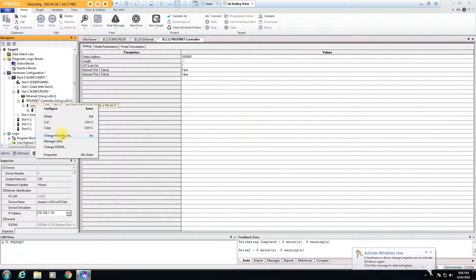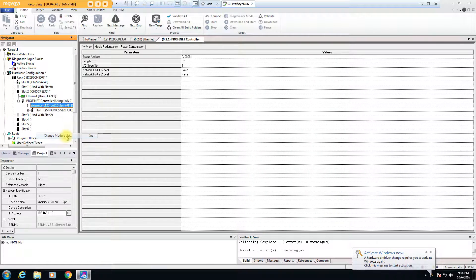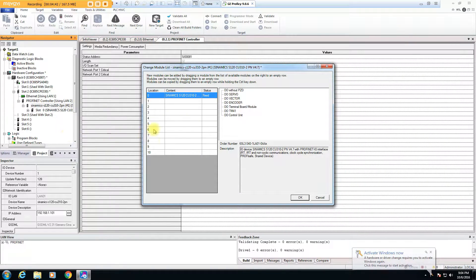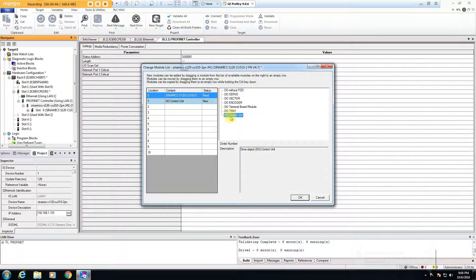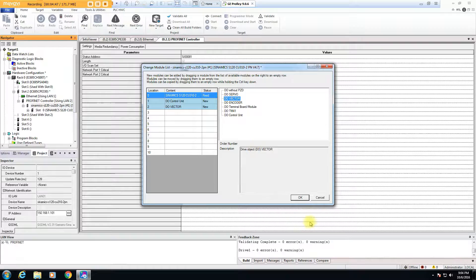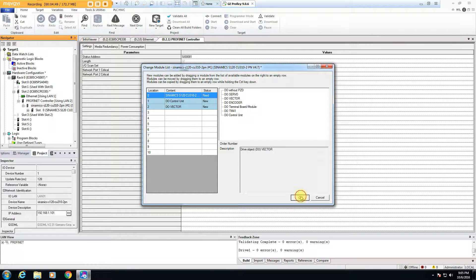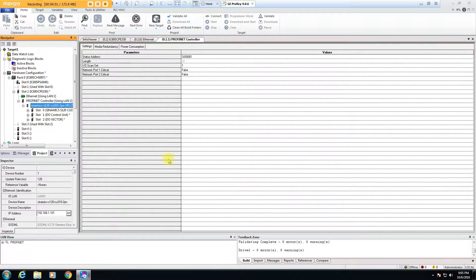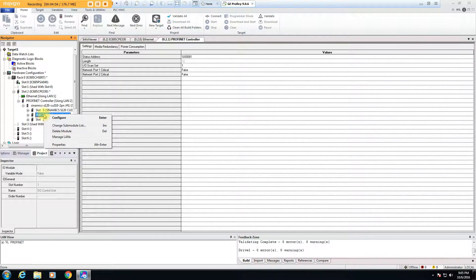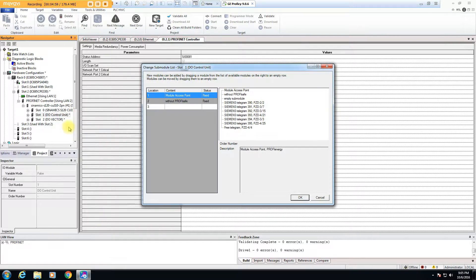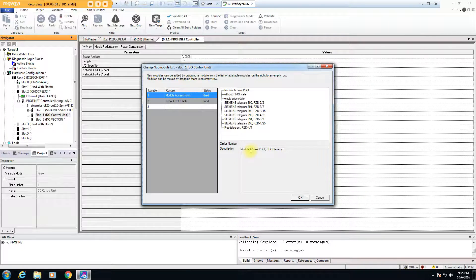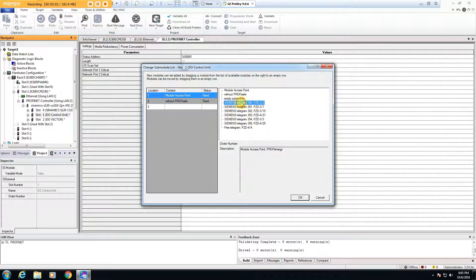But then you gotta go ahead and say now I have the drive, what kind of word exchange can I get. Like a lot of these Siemens system drives, they have the base control unit and then they have the actual vector or servo portion of the drive. So you put those two basic parts in, and then for each one of those you go in and pick how many words you want to exchange back and forth.